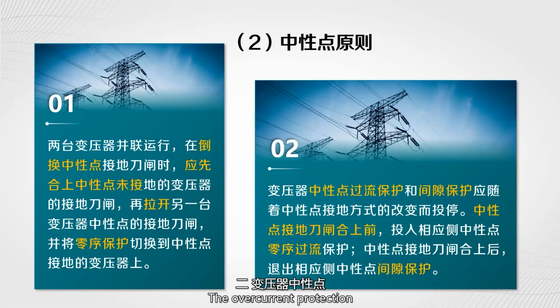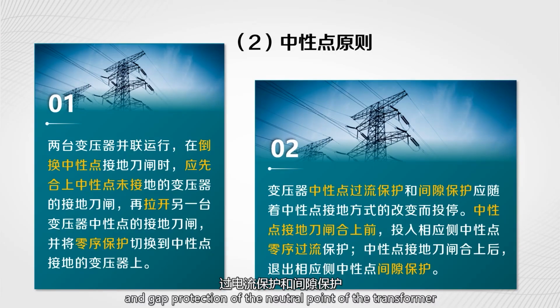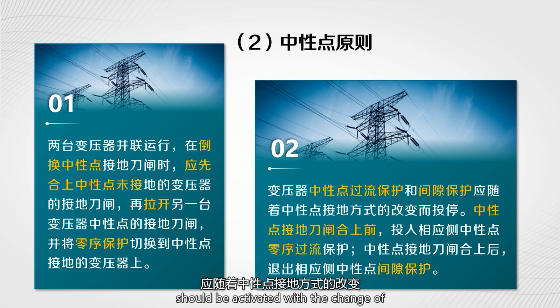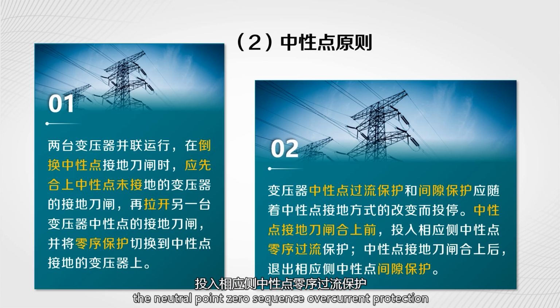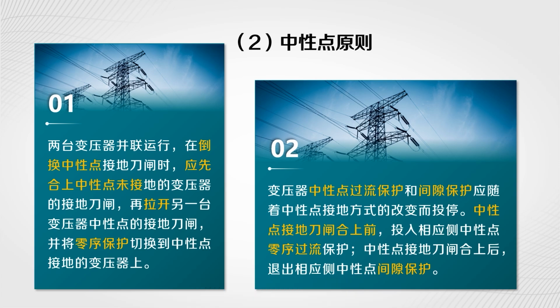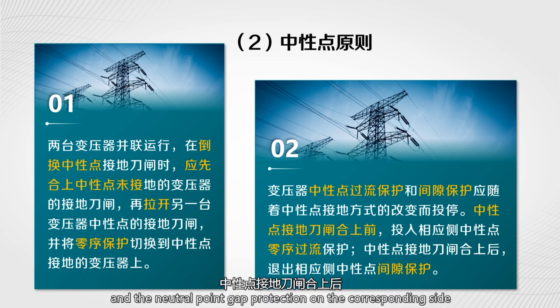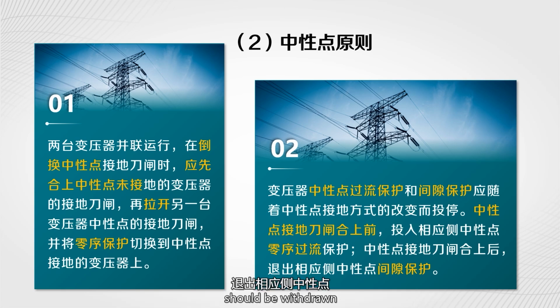The overcurrent protection and gap protection of the neutral point of the transformer should be activated with a change of the neutral point grounding method. Before the neutral point grounding switch is closed, the neutral point zero sequence overcurrent protection on the corresponding side should be put in, and the neutral point gap protection on the corresponding side should be withdrawn after the neutral grounding knife switch is closed.